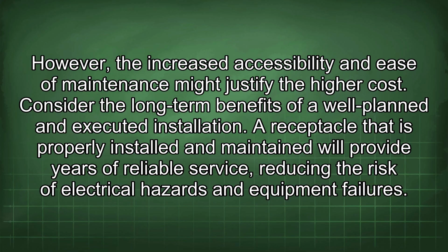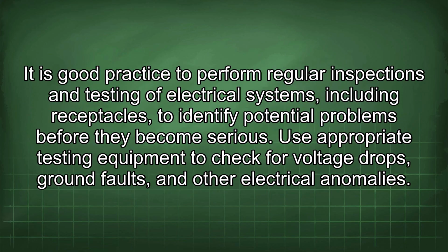A receptacle that is properly installed and maintained will provide years of reliable service, reducing the risk of electrical hazards and equipment failures. It is good practice to perform regular inspections and testing of electrical systems, including receptacles, to identify potential problems before they become serious. Use appropriate testing equipment to check for voltage drops, ground faults, and other electrical anomalies.